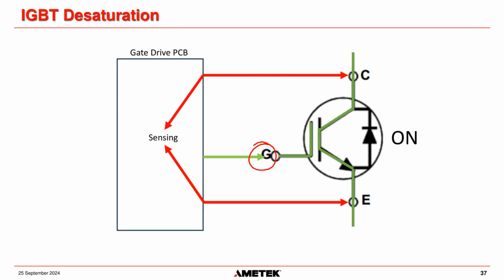When we do send a gate signal, we have a sensing circuit on the gate drive PCB that is looking at the collector voltage with respect to the emitter voltage. Now, when we turn it on, it should be a direct short. So theoretically, it should be 0 volts between the collector and the emitter, but no IGBT is perfect. Okay, and there is a voltage across that IGBT in normal operation. So we're measuring that voltage and we're comparing it. And basically what we're saying is, if it's less than 9 volts across the collector and the emitter when we're sending a signal to the gate, then that's okay. Everything is good. We will allow the system to keep switching the IGBT on and off.